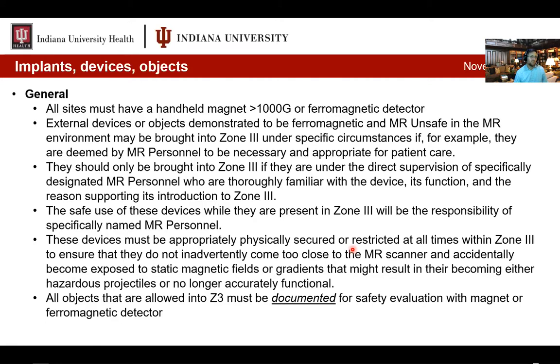External devices or objects demonstrated to be ferromagnetic and MR unsafe may be brought into Zone 3 under specific circumstances. For example, if they're deemed by MR personnel to be necessary for patient care, but they should be brought into Zone 3 under the direct supervision of specifically designated MR personnel who are thoroughly familiar with that device and its function. Safe use of these devices while they are present in Zone 3 is specifically the responsibility of a named MR personnel. These devices must be appropriately physically secured or restricted at all times in Zone 3 so that they do not inadvertently come close to the MR scanner and accidentally become exposed to static fields or gradients that might result in them becoming projectiles or potentially not being functional anymore.